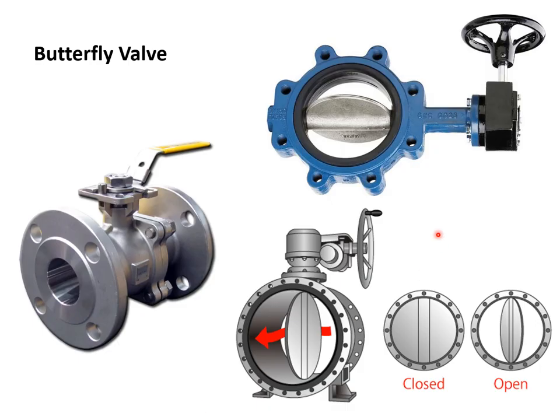This is the configuration of a butterfly valve, also used to control the flow of water in water supply pipelines. The difference between a ball valve and a butterfly valve is that a ball valve is suitable for small-diameter pipes up to 40 mm or 60 mm, whereas a butterfly valve can work very well in larger-diameter water supply pipelines. This is the disc — by just turning a quarter radius, the disc can be put in one direction or the other. If the disc is across the pipe, the supply line is closed; if the disc is aligned with the flow, this is the open supply line.